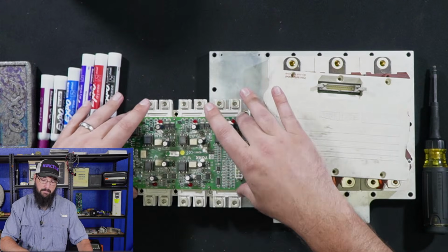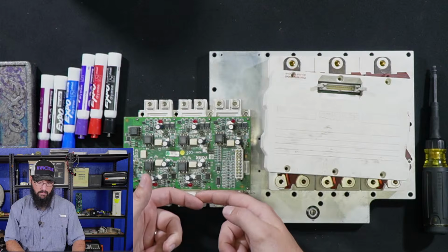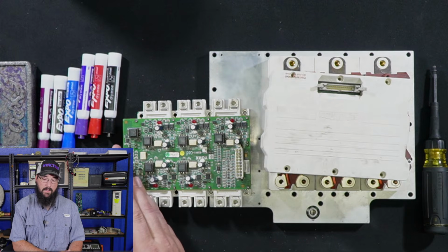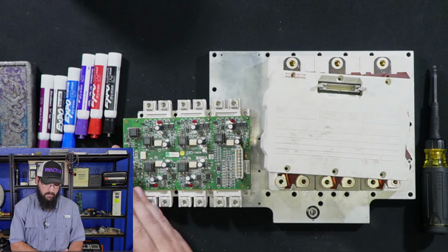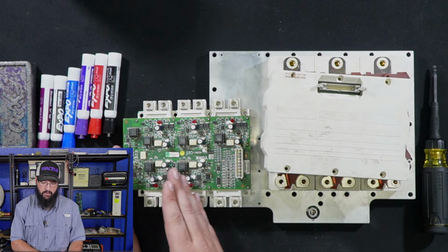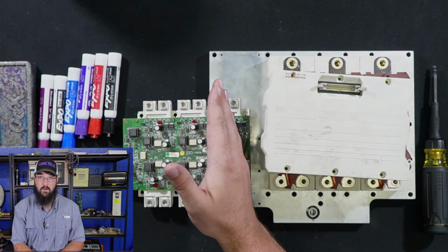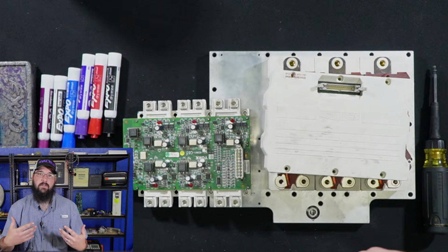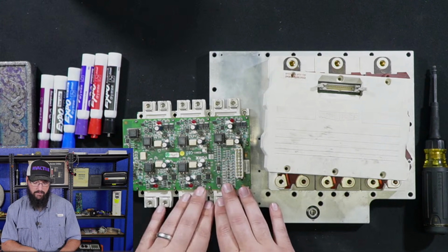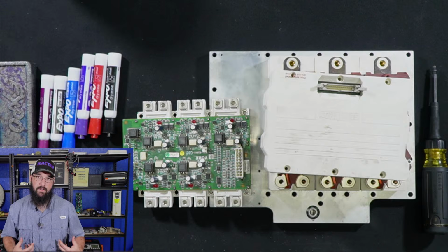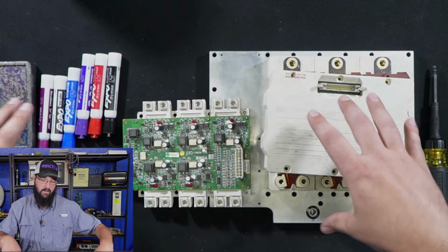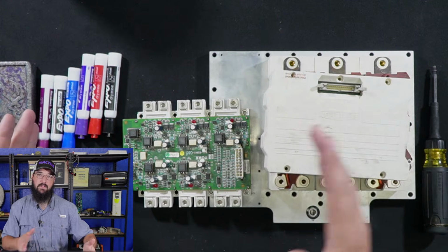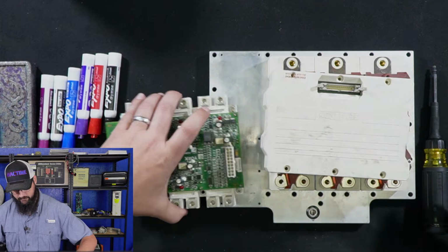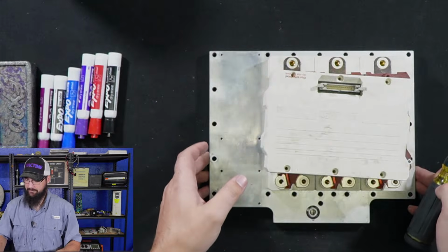So this may be one leg of power, and you'll have a solid bus bar coming across here. What that does is it distributes, say, A phase, or B, let's call it B's. So it distributes B phase's current across three modules instead of having one really large module to run just that one leg of power. So now we can have that distributed across the three, and then the three can carry that one phase, and then you'll have two other assemblies. So you'd have A, B, and C phase all coming out of each module. Anyway, fun stuff. Fun stuff. Make it situated here.